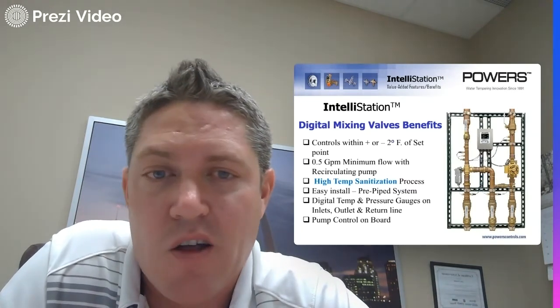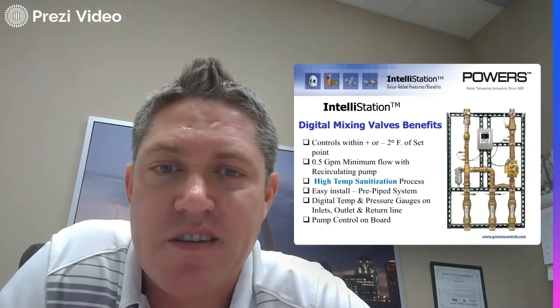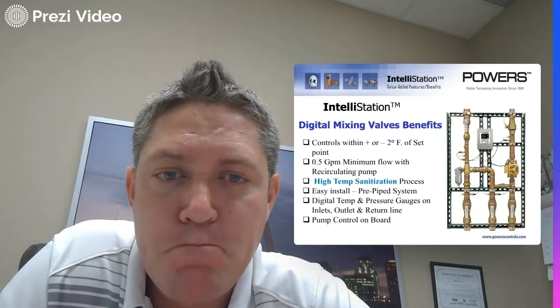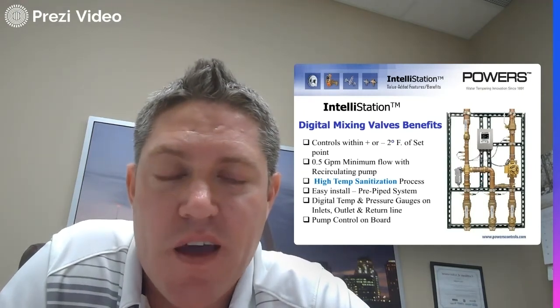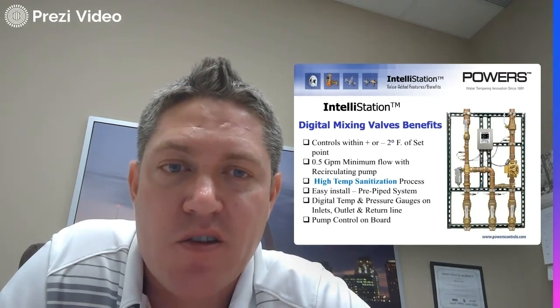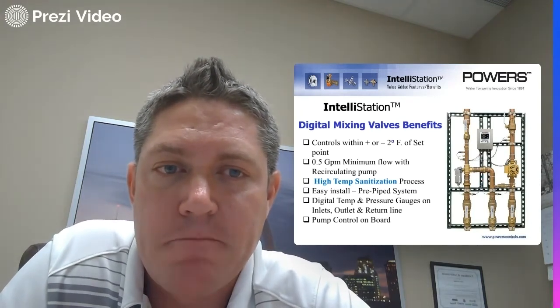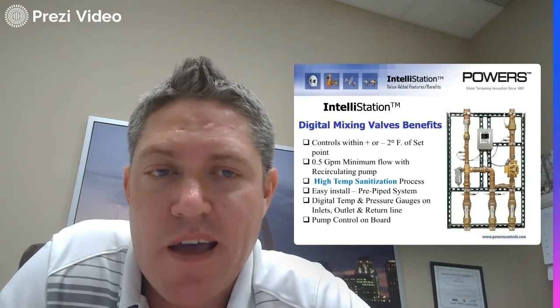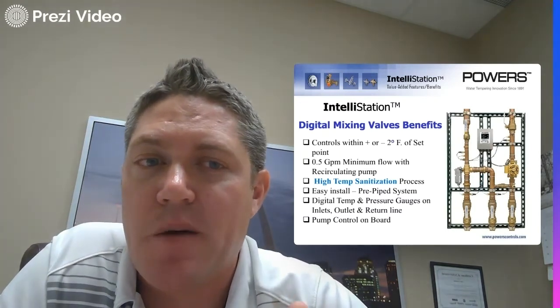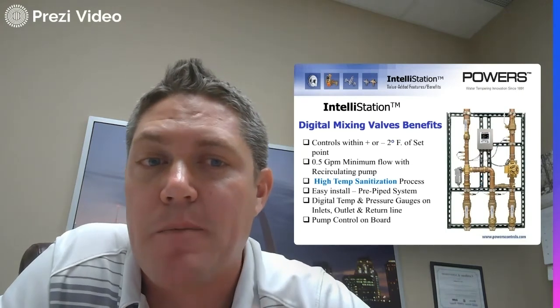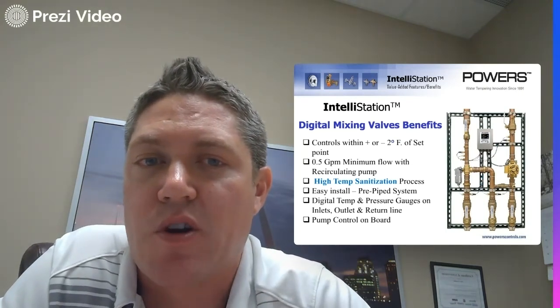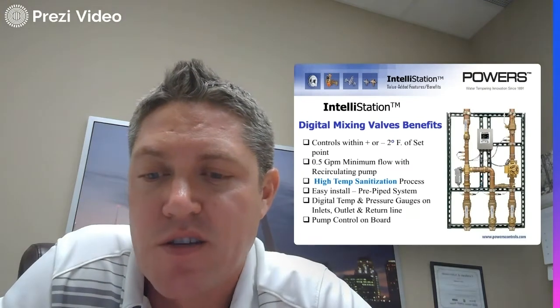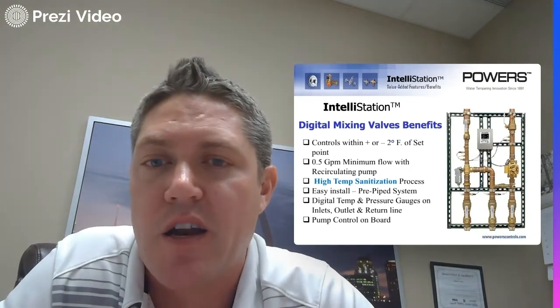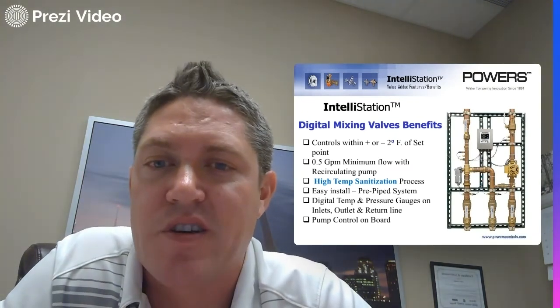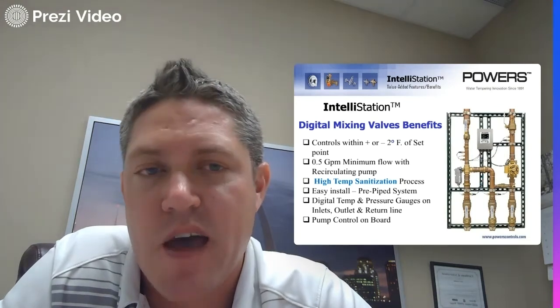The install is super easy, especially on the pre-pipe systems. Gauges for all that monitoring come on those pre-pipe systems. And pump control. As I said, you can order these with a pump or without a pump, but that pump can be controlled right through the controller on these digital mixing valves. So if you want it to turn off and on depending on the temperature coming back on the return, you can do that.